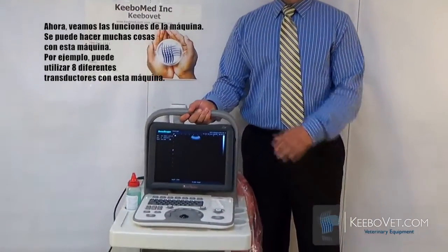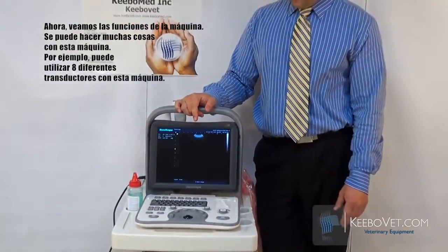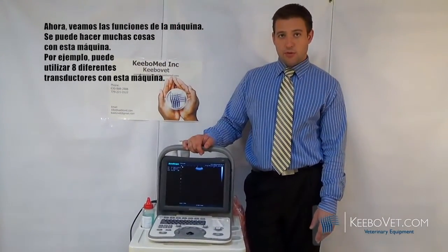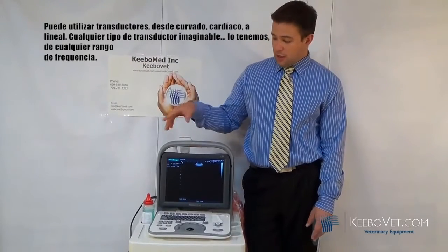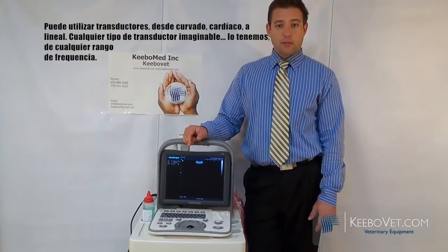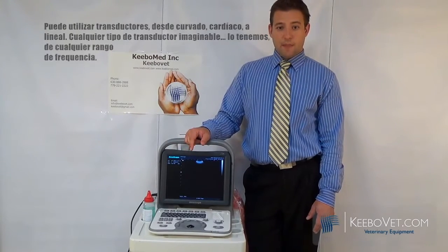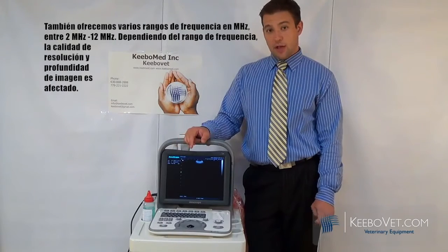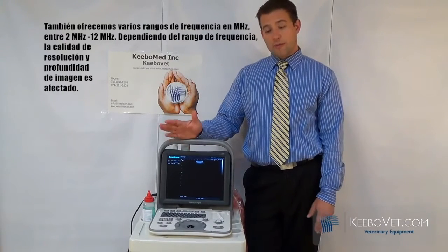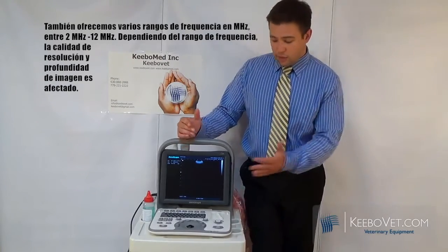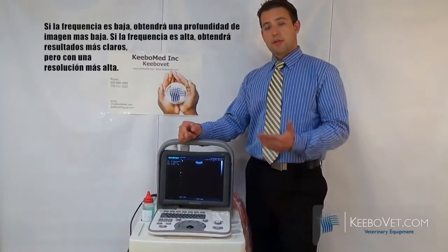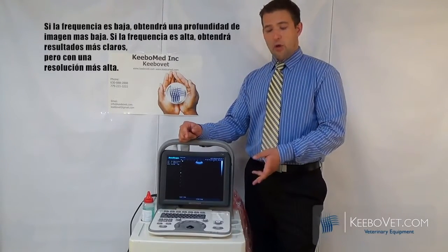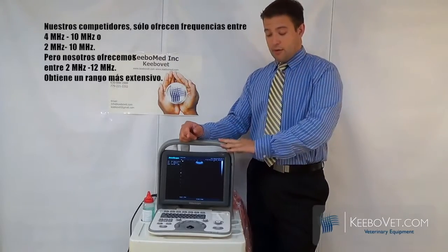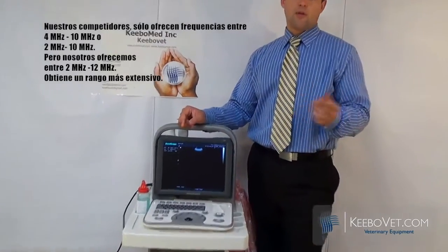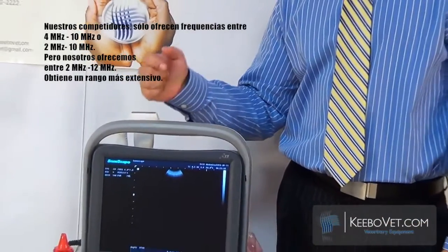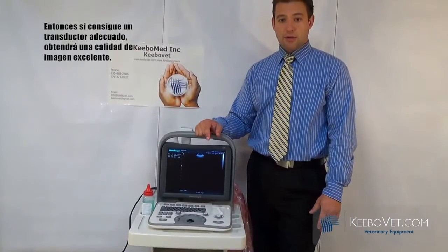Continuing on, functions. There are lots of different things that you can do with this machine. You have the ability to have up to 8 different transducers. Everything from curved, cardiac, linear, every probe imaginable, we have one that fits in the range. There's also the megahertz range itself. You can go from 2 megahertz to 12 megahertz. That is a function of image resolution and depth. The lower the frequency, the deeper you can go. The higher the frequency, the shallower you can go, but your resolution goes up. A lot of other competitors only have frequencies from 4 to 10, or 2 to 10, we go from 2 to 12. So you really get the whole broad range. So you find the right transducer for your application, and you'll be able to get great images.